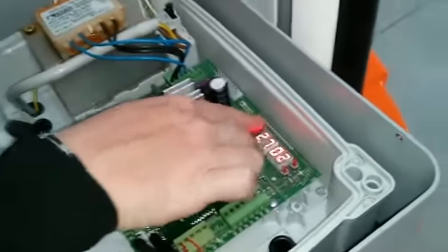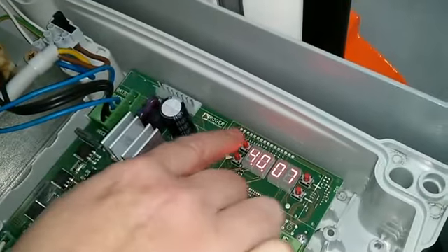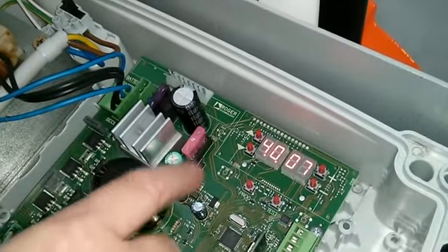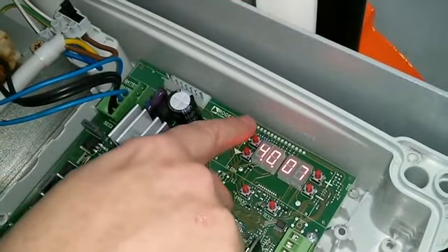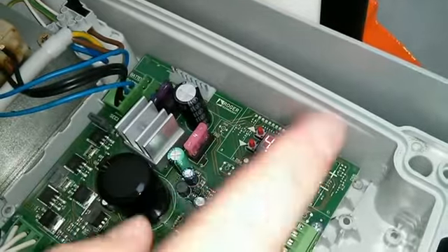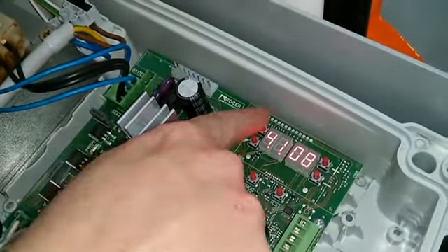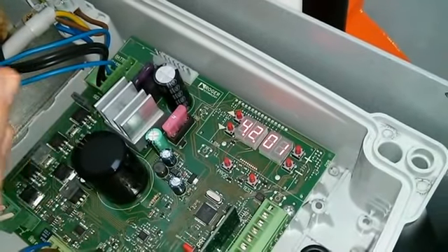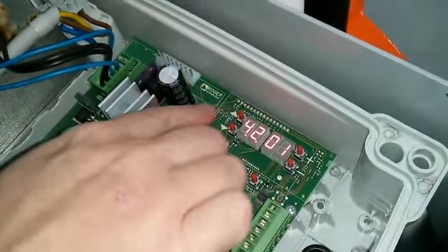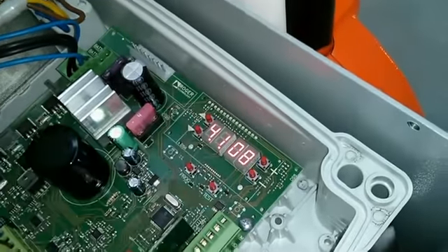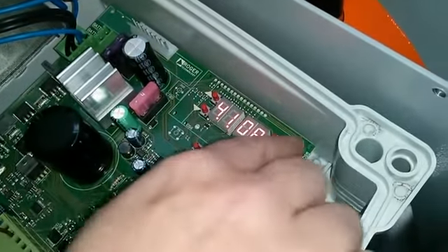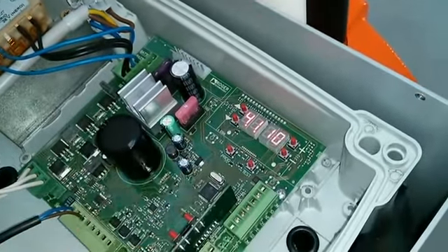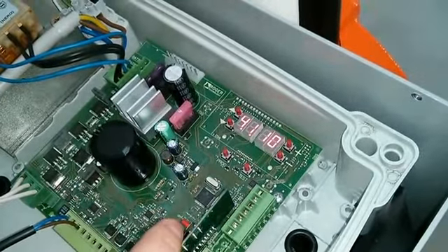For example, for the speed, I can without any problem set or preset the default value of the parameters, for example the speed in opening, like parameter 41, or the speed when I'm going to close. If I want to go faster when opening, I go to parameter 41 and can fix 10 as the value. It means I have 100% of the speed available in opening.